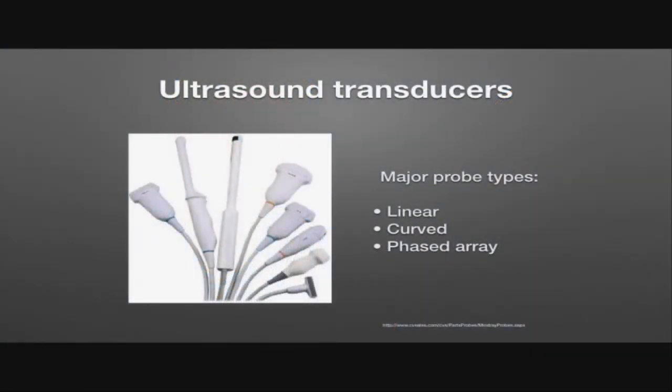Transducers convert energy — they transfer electrical energy into sound energy. Ultrasound crystals are bi-directional, meaning they can transfer electrical energy into sound energy and then convert sound energy back into electrical energy. Different transducers have different ultrasound crystals with a natural frequency, allowing them to operate at maximum efficiency. This is like a guitar with strings vibrating at different frequencies, with different probes operating at their maximal frequency in terms of both operating frequency and bandwidth.